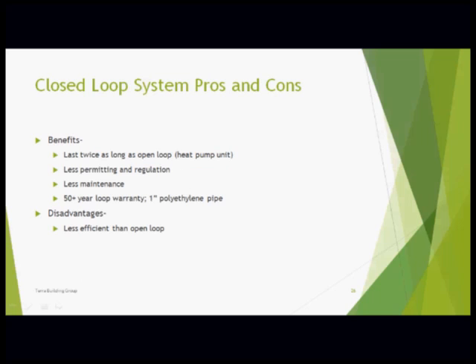Closed loop benefits. The units inside last twice as long with a closed loop system in general. The reason is you're recirculating the same solution. You're not bringing in sediments, hard water, those types of things. You have less permitting and regulation. In some cases, you have none. Less maintenance. The loop is 50-plus year warranty. Disadvantage, it's slightly less efficient than an open loop. Since you're not pulling in the heat or cooling source directly, it's a transfer, you lose some efficiency.